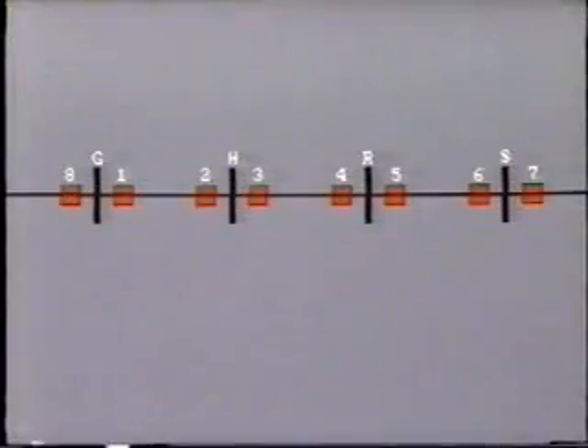On most high voltage lines, particularly interconnected transmission systems, the preferred method of protection is by the installation of distance relays. Let's look at the basic application of distance relays to part of a power system. First, we'll focus our attention on the bus G location.